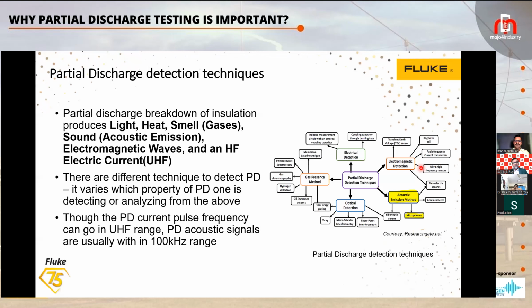This is the time we have actually launched an acoustic emission method. It was there previously also, but what we have done is come out with an acoustic detector, or acoustic imager, which can really detect the partial discharge and tell you what kind of partial discharge it is and exactly where it is. That is what we have done in 2020.